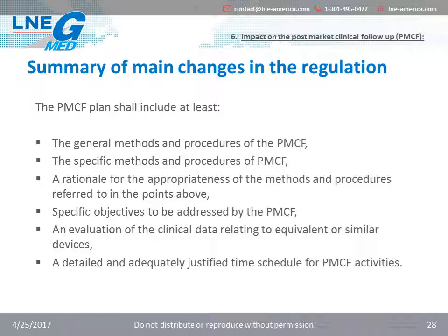an evaluation of the clinical data relating to equivalent or similar devices, and finally, a detailed and adequately justified time schedule for the post-market clinical follow-up activities. For example, analysis of post-market clinical follow-up data and reporting to be undertaken by the manufacturers. So the manufacturers shall analyze the findings of the post-market clinical follow-up and document the results in the post-market clinical follow-up evaluation report that shall be part of the clinical evaluation report and the technical documentation.